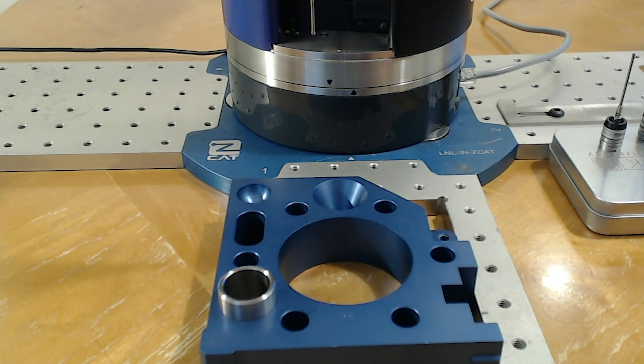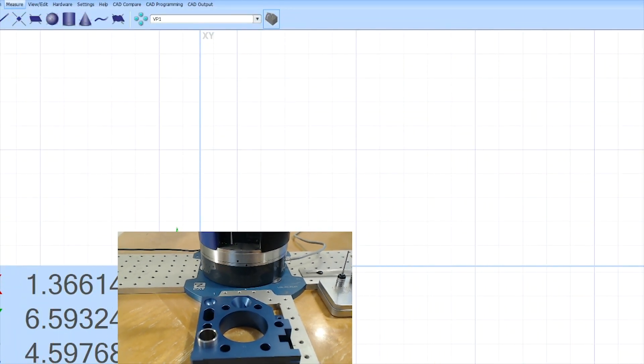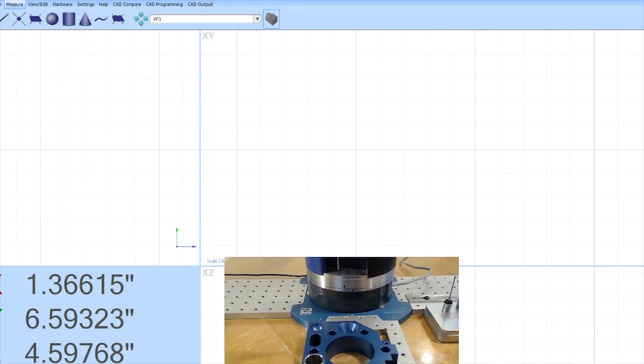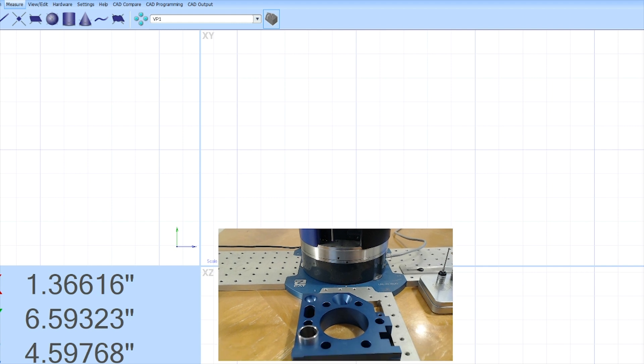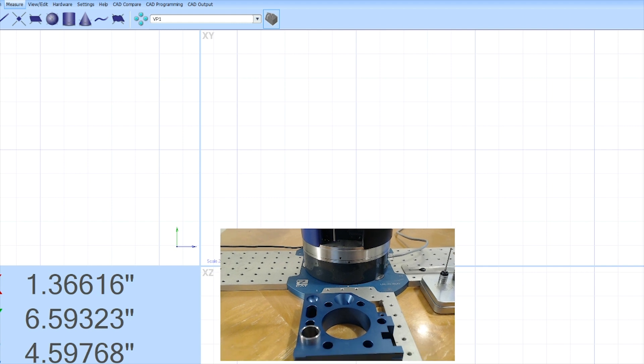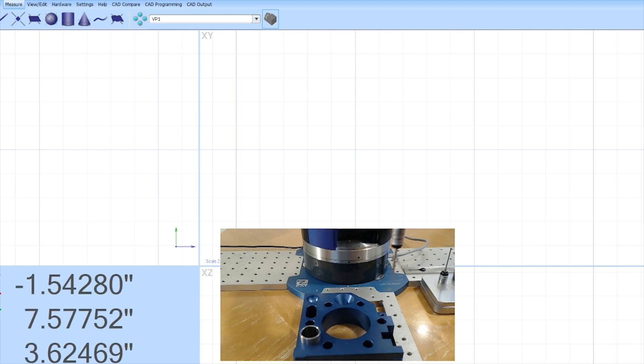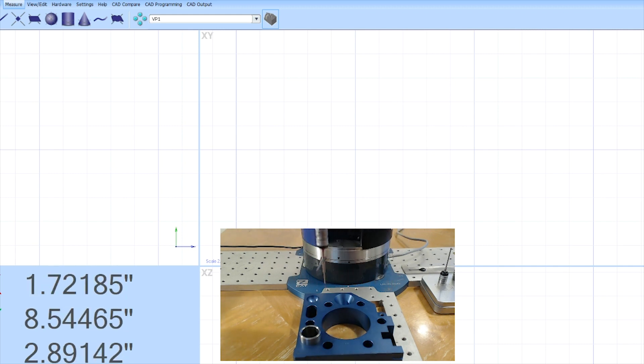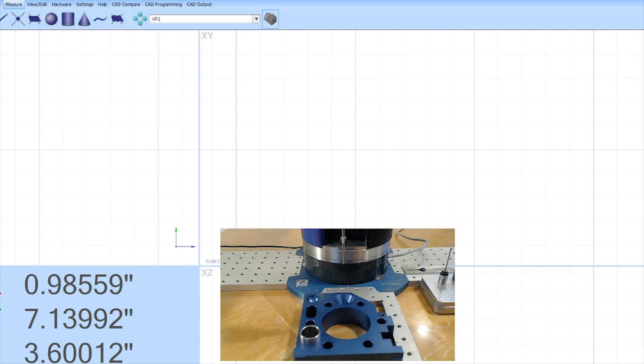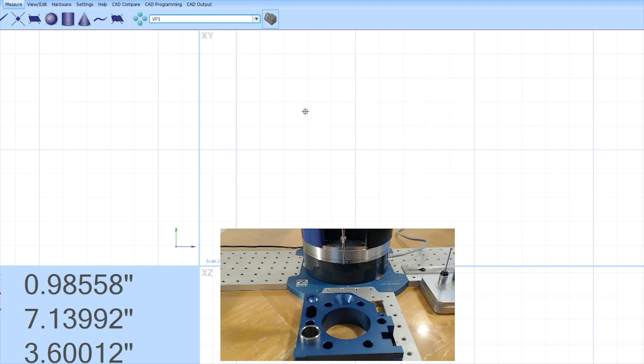So now that I have my part oriented, I'm going to minimize my screen a little bit here, my camera, and bring up the computer screen. Now once it's booted up and connected to the ZCAT, you can see as I move the ZCAT around my digital readout will move accordingly. It's using the active probe. In this case I have vertical probe one chosen as my active probe. I do have a drop-down window that will allow me to show whatever probes I have available. We're going to stick with vertical probe one right now.